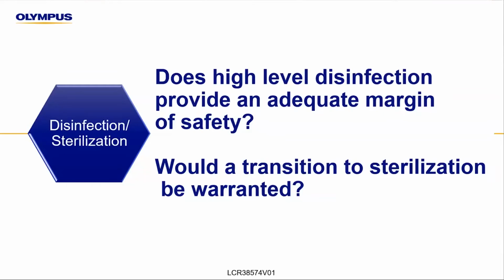Yeah, I agree with you. I think people have to think all the way down the road, not just knee-jerk to think that sterilization is the solution to all the problems. There are many different levels of things that need to be considered, not the least of which is the logistics. If you're sending it for ETO sterilization, most sites don't have that on site and they have to send it off site. And gosh, don't send a wet scope in transit for a day and a half to the ETO sterilization site, because you're going to have bacterial replication. And like I mentioned, if you do get biofilm formation, the sterilization isn't going to work either.